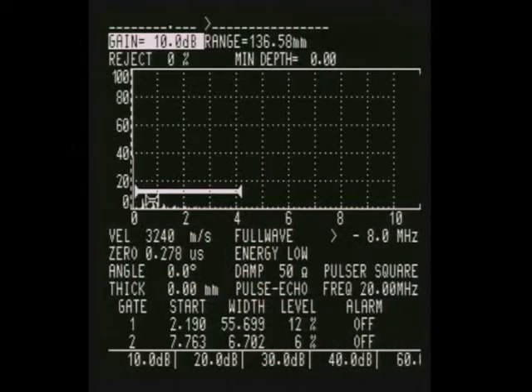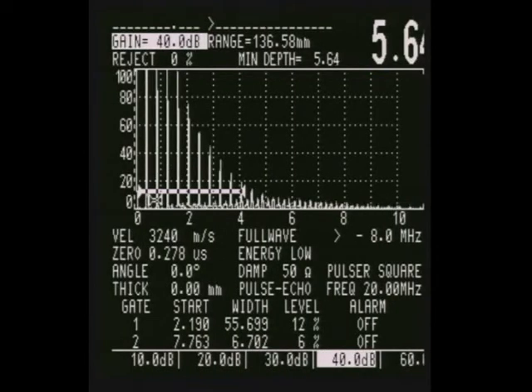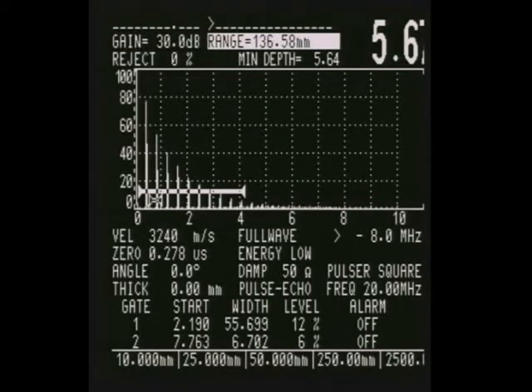We're going to place the probe on a 10mm step. And our screen is still blank. So we're going to go through the velocity, or the gain, mind you. And then we're going to figure out where we get a nice echo train.